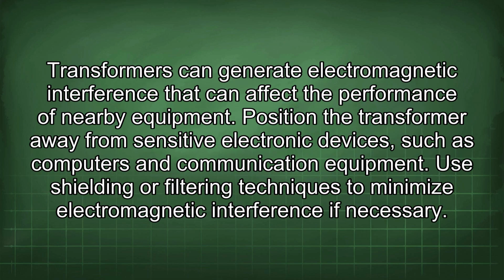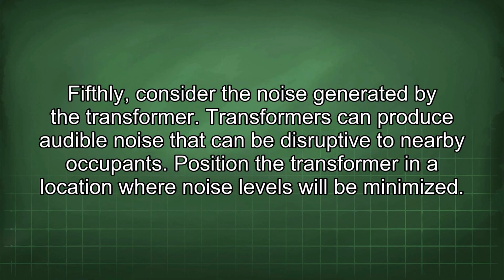Transformers can generate electromagnetic interference that can affect the performance of nearby equipment. Position the transformer away from sensitive electronic devices, such as computers and communication equipment. Use shielding or filtering techniques to minimize electromagnetic interference if necessary. Fifthly, consider the noise generated by the transformer.